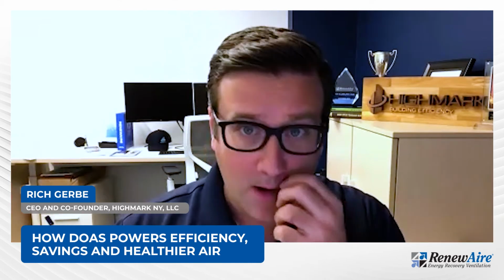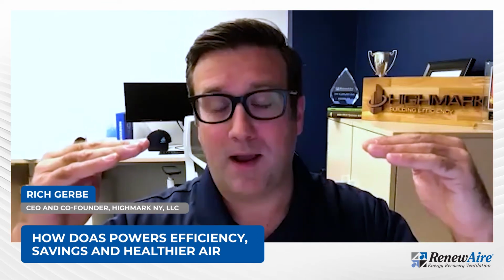The reality is, when you think about a building with a traditional ceiling, with air coming in and out of vents, you've got a conditioned airstream and an unconditioned airstream on a crash course collision, creating huge thermal comfort issues inside the building. What's great about DOAS systems is that, by the way the physics and psychrometrics work, we're able to deliver air very close to the temperature we're controlling the spaces to. Because of that, we can go directly to the zone, which is a great energy saving, a great money saving, and saves us in terms of ductwork and complexity.